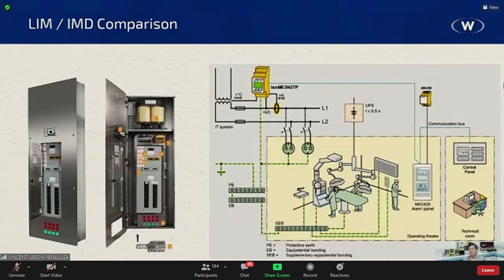Now, for the insulation monitoring devices, you have that little yellow box. You have the isolation transformer, which is again no more than 10 kVA. It will have a temperature sensor, the same as the line isolation monitor. You will also have a small CT to measure load, to measure current. Why is this important? Because this is going to be part of the alarm. This is also one of the differences between the industrial kind of insulation monitoring device and the hospital grade monitoring device. Here, you have connections for load monitoring as well as temperature monitoring of the transformer. Why? Remember, you only have 10 kVA. It's a small transformer. It's going to be easy to overload it. And you guys know for a fact that a nice way of loading your transformers would be around 80%. That's where it's most efficient.